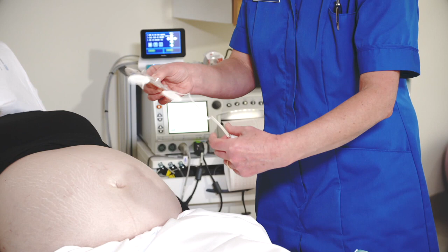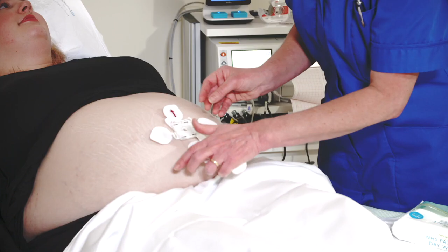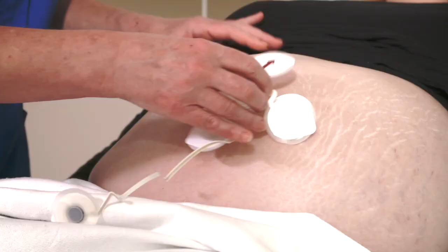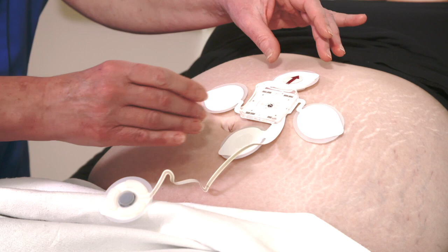Place the patch firmly down so that the clip is centered on the umbilicus, with the red arrow on the top electrode pointing towards the mom's head. If the mom has a piercing or other problem with the umbilicus or the skin area around the umbilicus where the electrodes will go, just move the clip to avoid the problem.